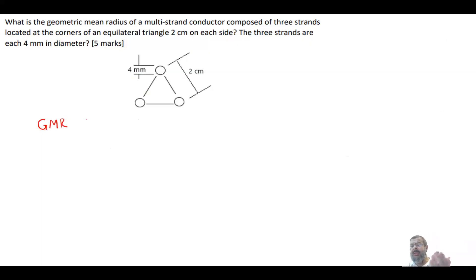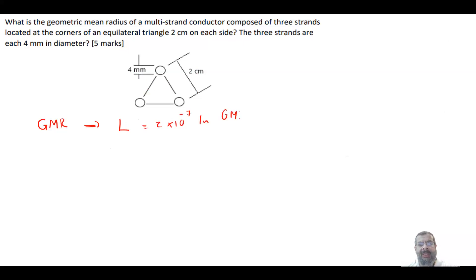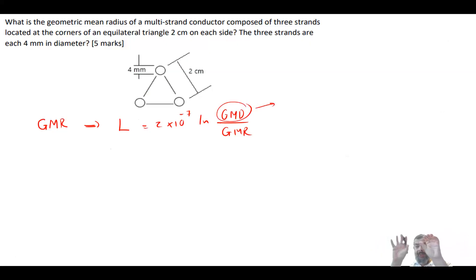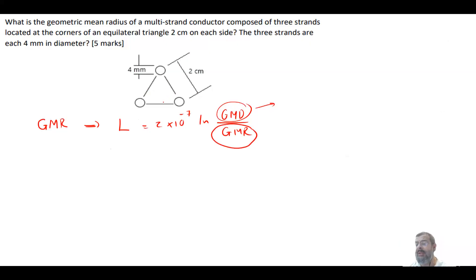GMR is important because the inductance of an overhead line equals 2×10⁻⁷ times ln(GMD/GMR), where GMD is the geometric mean distance — basically the distance between the three phases — and GMR is the distance within the phase itself. This is called a bundle conductor, so it's just one phase, and we need to find its GMR.